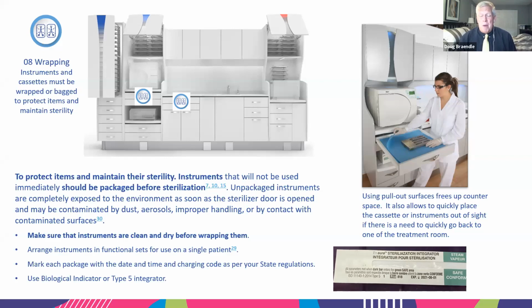So what I recommend is just take a regular pouch, put one of these type 5 integrators in that pouch, seal it. Now you make it a challenge device. And what I recommend is put that in the middle, whether you're doing pouches or cassettes, put that in the middle of the load of whatever sterilizer you're using, and then use that, in my vernacular, as a load release indicator. So whoever is tending to the sterilization area, after the cycle, after the machine says we're done, you open up the door, and then you reach in and you pull out this integrator and you take a look.